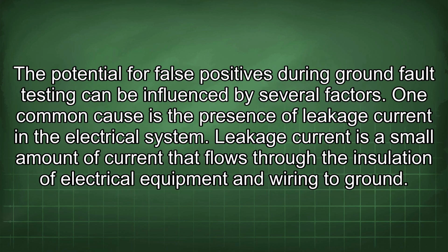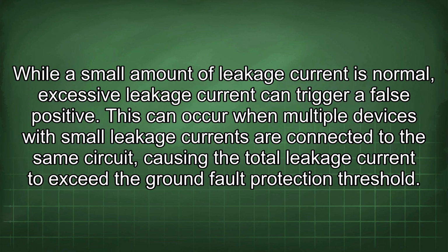The potential for false positives during ground fault testing can be influenced by several factors. One common cause is the presence of leakage current in the electrical system. Leakage current is a small amount of current that flows through the insulation of electrical equipment and wiring to ground. While a small amount of leakage current is normal, excessive leakage current can trigger a false positive. This can occur when multiple devices with small leakage currents are connected to the same circuit, causing the total leakage current to exceed the ground fault protection threshold.